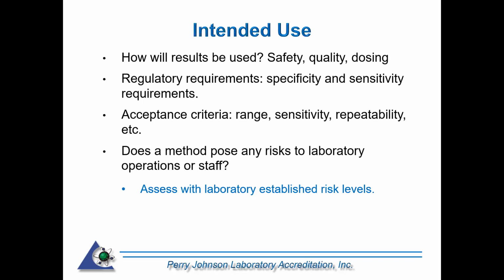Making sure that you are using your intended use then as you're looking at what the acceptance criteria are. What does a method have to be able to achieve in order to be acceptable as the right method for us as a laboratory, for what we are reporting out there and what our clients need, why they need the information. So that's going to be looking at your reporting ranges, sensitivity, repeatability, et cetera. Those things need to be set before you run the study.